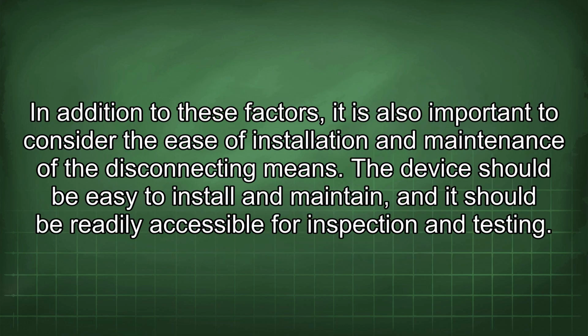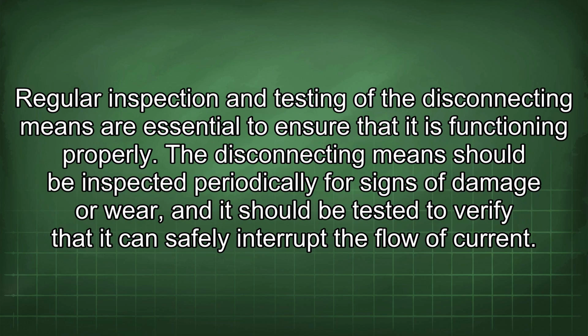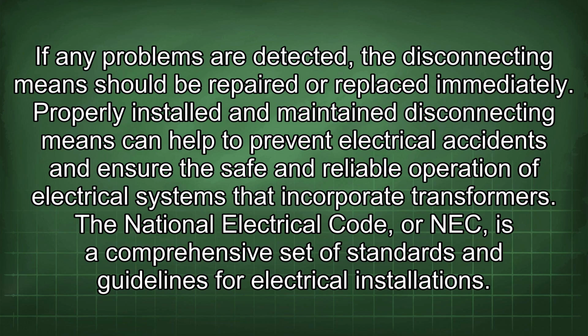In addition to these factors, it is also important to consider the ease of installation and maintenance of the disconnecting means. The device should be easy to install and maintain, and it should be readily accessible for inspection and testing. Regular inspection and testing of the disconnecting means are essential to ensure that it is functioning properly. The disconnecting means should be inspected periodically for signs of damage or wear, and it should be tested to verify that it can safely interrupt the flow of current. If any problems are detected, the disconnecting means should be repaired or replaced immediately.